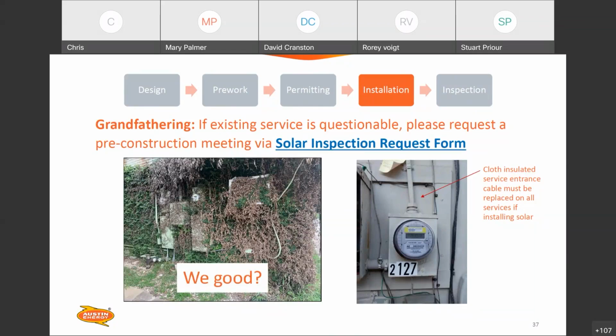One thing I didn't mention in here, if you've got a residential Federal panel, and you old timers out there know what I'm talking about, that's going to have to be replaced. Just a note, if it's a Federal panel on a residential house, that panel needs to be replaced if you're going to add solar to that. And again, if you're an old timer like me, you know what I'm talking about, because those breakers have been known not to trip. That's the reason.